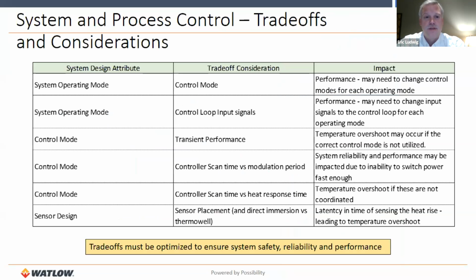So again, some of the trade-off considerations here associated with the control mode and the operating system. We talked a little bit about understanding which operating modes you would use in each control mode. If you've got more of a steady state operation, then you can use more of an on-off type control system, and a straight PID loop may work. Whereas if you've got a lot of transients in a particular operating mode, then you want to use kind of a feed-forward PID system. So these control modes also have influence over transient performance.